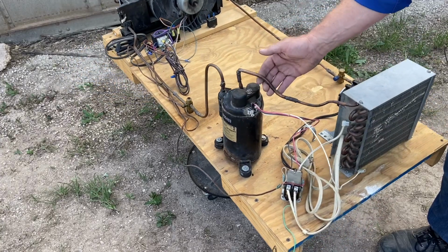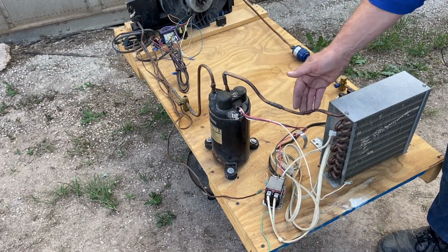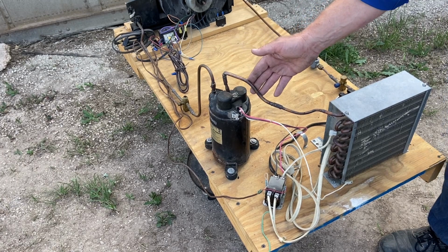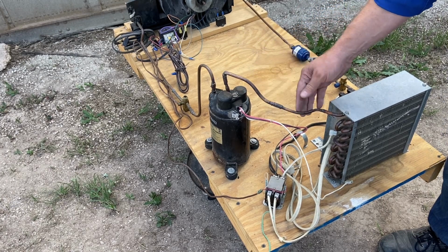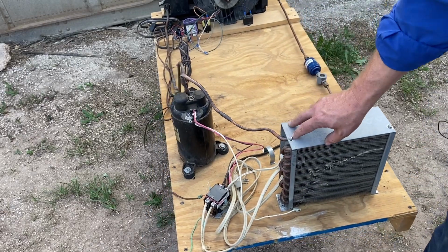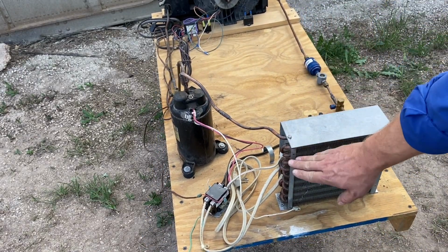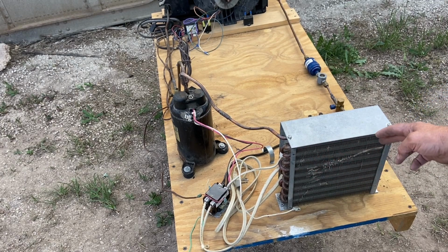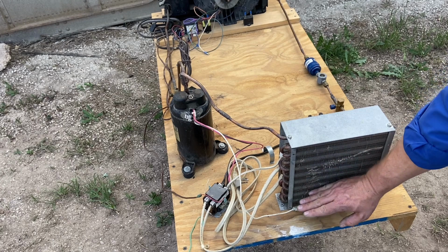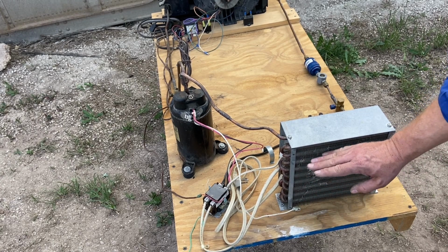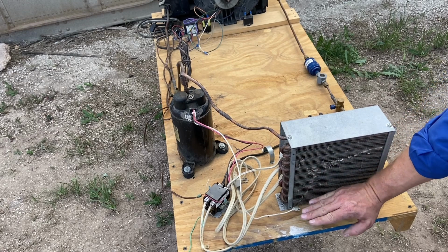Then we have our discharge line, also called a hot gas line, the shortest line in the system. This refrigerant is a high temperature, high pressure superheated vapor. From there we go into our condensing coil, and the very first little section of this condensing coil is going to de-superheat. It's all sensible, very little BTUs released, but big temperature change. The rest of this condensing coil is going to be condensing. That's going to be latent heat, changing state from a vapor to a liquid.